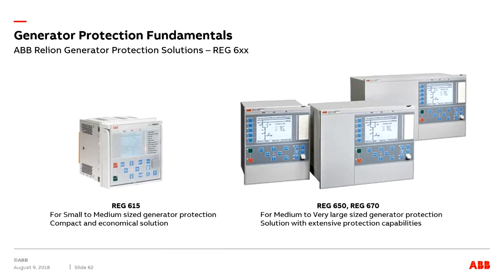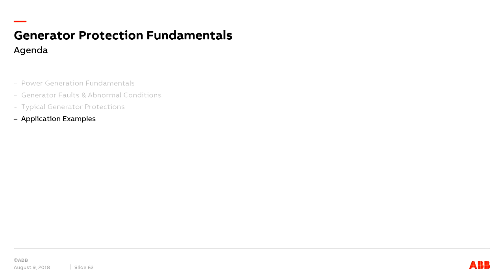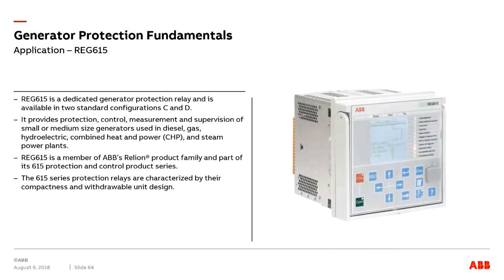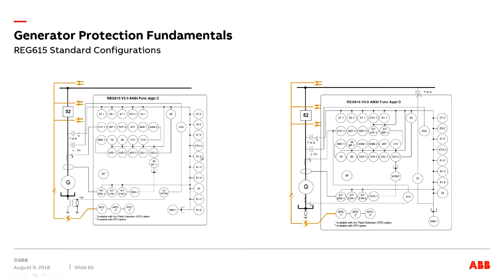I know that it's been quick on some of the protection elements, but maybe I'll take a couple of minutes more to just run through some application examples. For example, REG615, it's a very compact design. It provides protection, control, measurement, and supervision of small to medium-sized generators used in diesel, gas, hydroelectric, combined heat and power, and steam power plants. So it comes in two different configurations, configuration C and D, as we can see here. And it also comes with 100% stator earth fault protection.